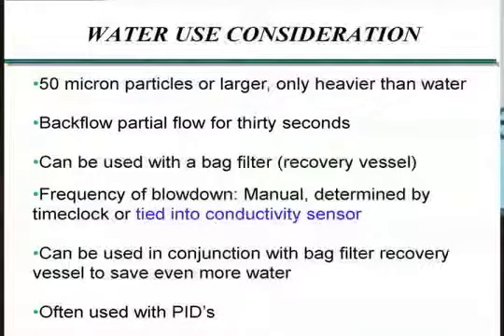It uses very little water compared to a sand filter. There's only a partial flow of water for 30 seconds. It usually ends up being 20 to 30 gallons, plus or minus, depending on the size of the system. And that water could be run back through a bag filter if you really want to maximize your water conservation. So from a water conservation point of view, this might be a preferable way to go, if it does what you want it to do.